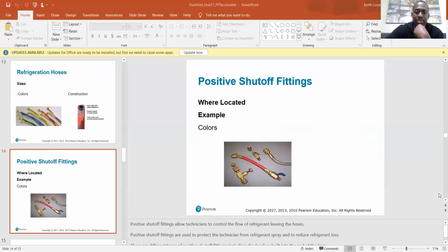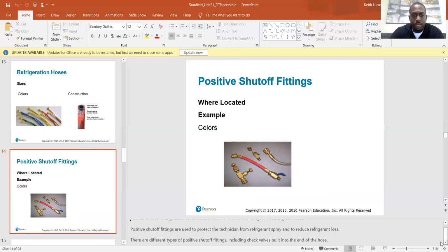Positive shutoff fittings. Positive shutoff fittings allow technicians to control the flow of refrigerant leaving the hoses. They are used to protect the technician from refrigerant spray and reduce refrigerant loss. There are different types of positive shutoff fittings, including check valves built into the end of a hose, which is a low loss fitting. That's when there's a check valve built inside of your hose, and when the pressure is released from that valve, it closes. And like every check valve, it allows flow in one direction and not the other. So once pressure is released off of that valve, it won't allow any refrigerant back out of that hose.